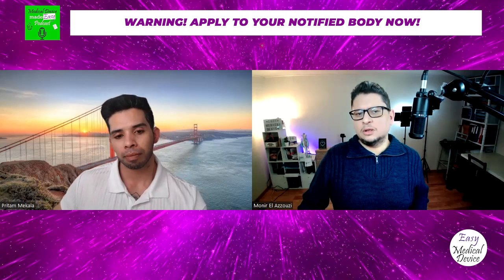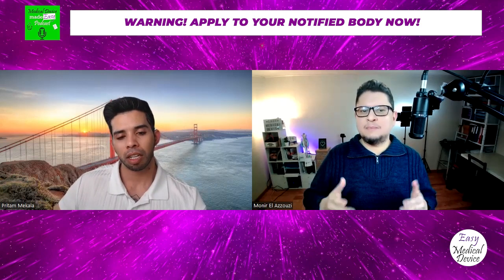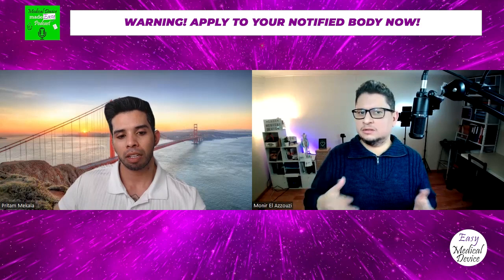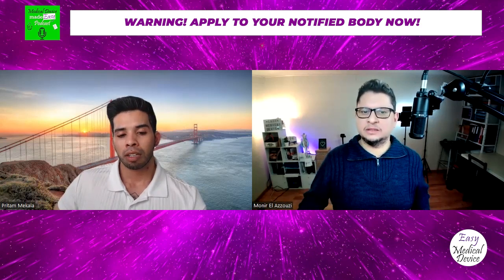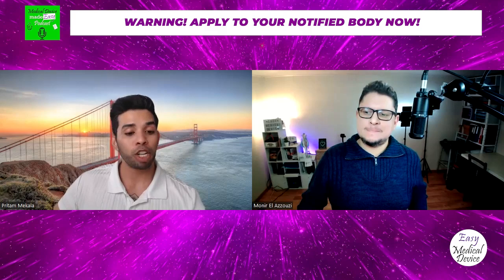Yeah. So can we say that this is applicable for any notified body, or it's just you who has built that mainly? It is applicable for any notified body. If you look at one of the latest MDCG guidance documents, MDCG 2022-14, when it was established, it specifically talked about structured dialogues being offered, or shall be offered, by notified bodies. So this is across the board, and regulations have already said that notified bodies have to do this, or at least have to provide the service for the clients.